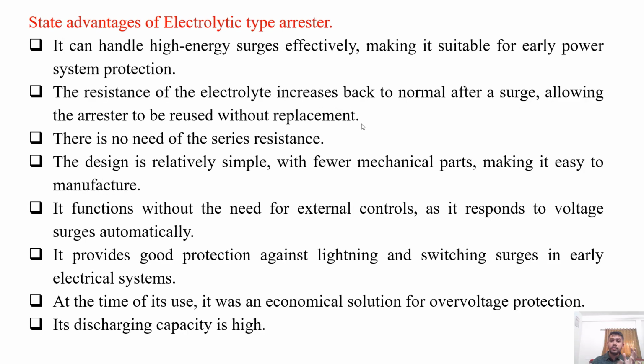State the advantages of the electrolytic type arrestor. So there are several advantages of this electrolytic type arrestor. Some are listed over here. It can handle high energy surges effectively, making it suitable for early power system protection. The resistance of the electrolyte increases back to its normal after a surge, allowing the arrestor to be reused without replacement. There is no need for series resistance in this case.